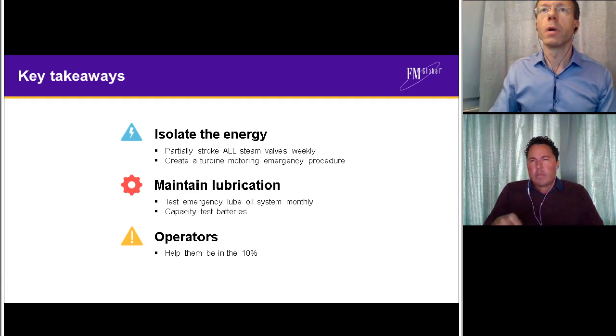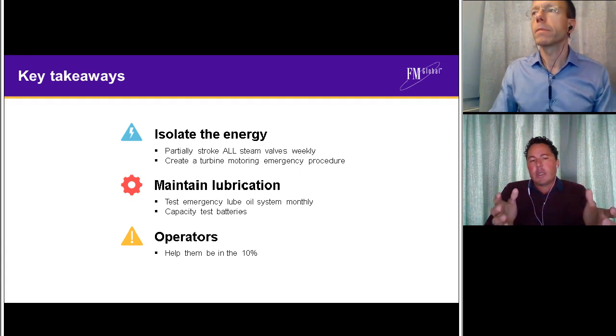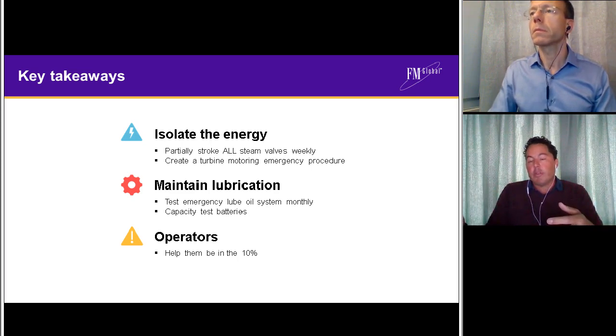Next question is from Vikram from Unison, who says, can you please again explain the hazard and why DC pump supply should bypass oil coolers and oil filters? Absolutely, Vikram. The challenge here is that you're introducing a common failure mechanism between the main oil supply and the emergency oil supply. So if, for instance, your standard setup has a duplex filter arrangement, ordinarily what happens is you run one of those filters until you get high differential pressure across the filter, you change over to the next filter, and all is well with the world.